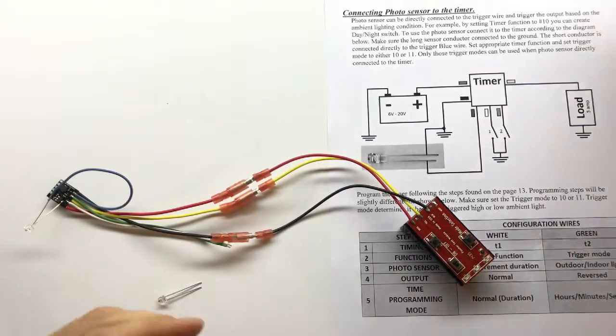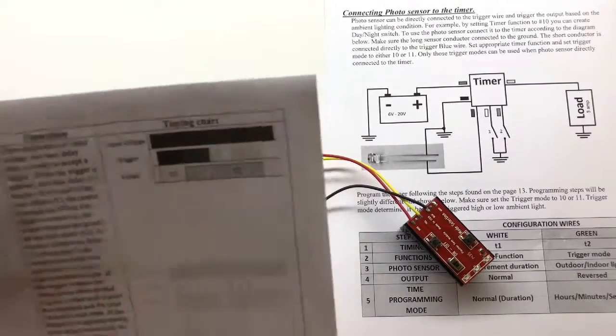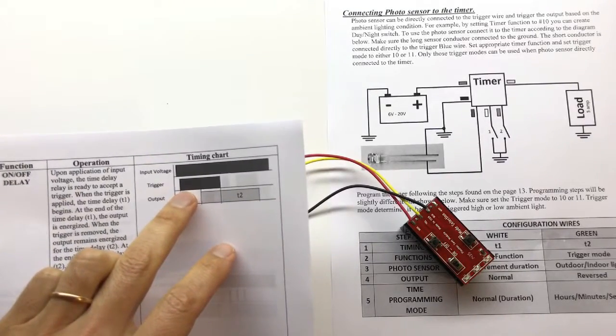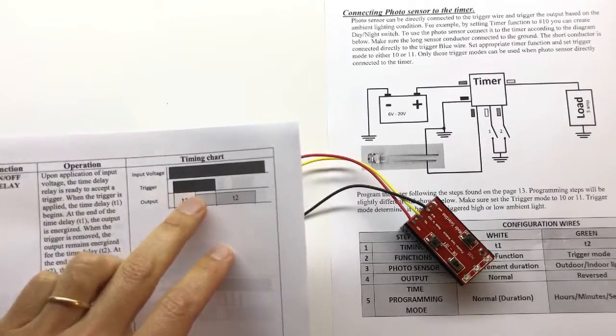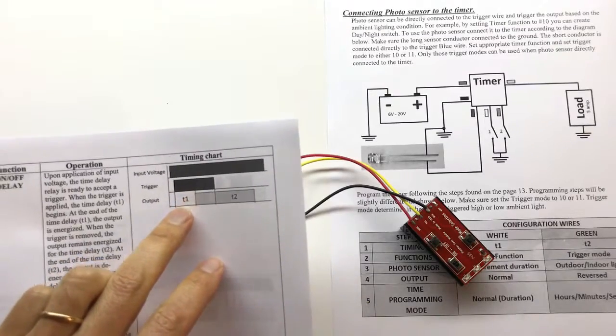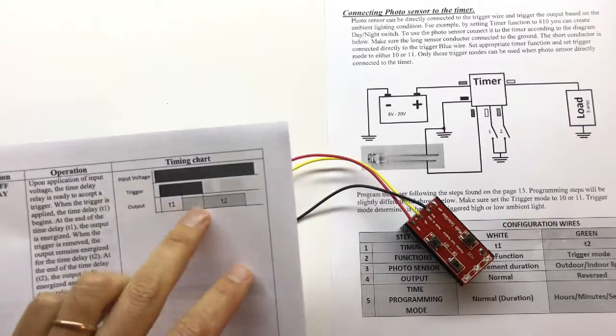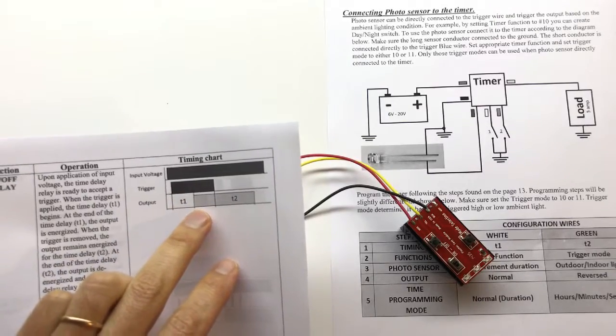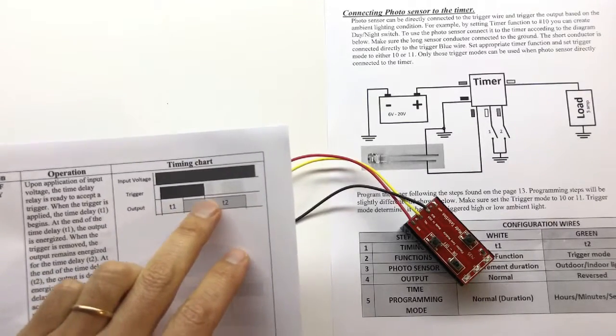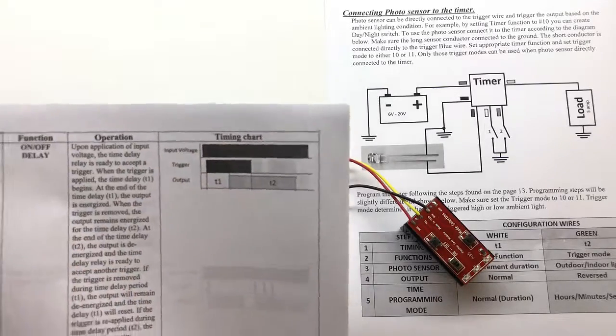So I'm just going to show you a couple of examples. For example, function 10. If we use the function 10 and set the trigger to the sun down, then we will set the T1 and T2 to very short time. So the sun down will trigger the output and it will be on until the sun rise and will turn off.